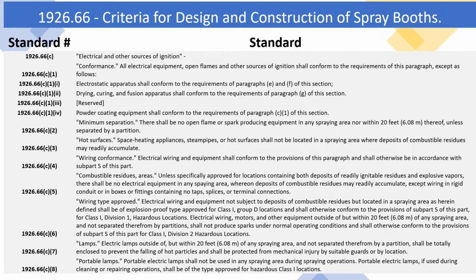Electrical wiring, motors, and other equipment outside of but within 20 feet (6.08 meters) of any spraying area, and not separated therefrom by partitions, shall not produce sparks under normal operating conditions and shall otherwise conform to the provisions of Subpart S of this part for Class I, Division 2 hazardous locations. 1926.66(c)(7) Lamps. Electric lamps outside of, but within 20 feet (6.08 meters) of any spraying area, and not separated therefrom by a partition, shall be totally enclosed to prevent the falling of hot particles and shall be protected from mechanical injury by suitable guards or by location.